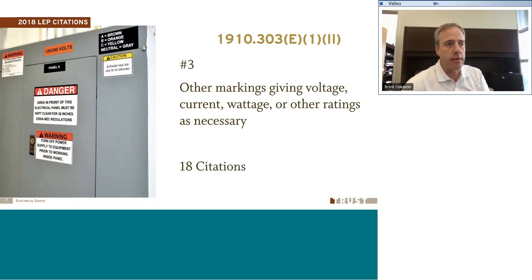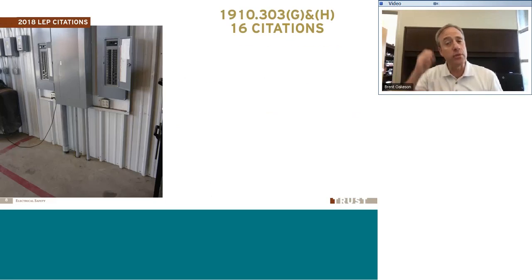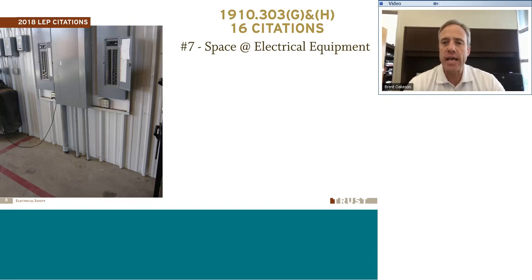Another one that we're looking at that was really common was just the space around electrical equipment. And generally this is electrical panels, and if you've been with us when we've done one of our inspections, we look at these things every single time, and this is a pretty common one. Not just electrical panels though. If you've got small transformers or different electrical power equipment in your facilities, this will apply there as well. So the standard has certain space requirements around the electrical panels. Your standard electrical panels that you have in most of your buildings need to be as wide as the electrical service panel or 30 inches, whichever is greater.